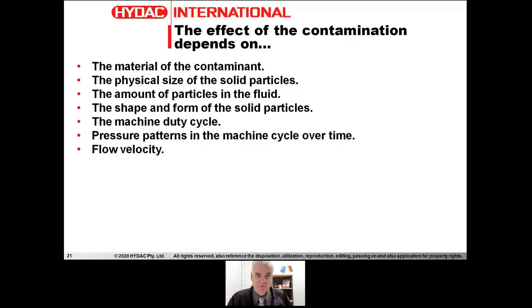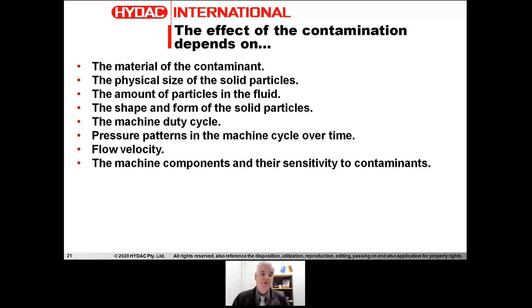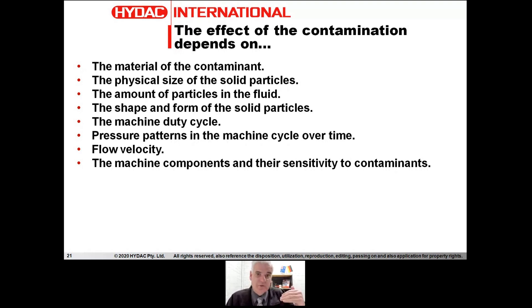Flow velocity has an effect as well — with regards to erosive wear, higher velocity in the fluid causes more erosion, so a high-velocity dirty fluid is more damaging than a low-velocity clean fluid. And finally, the machine components and their sensitivity to contaminants: how much contamination a system can tolerate depends a lot on the system itself, coming down to the clearances involved in the components. These are things we'll look at later when we're choosing the media.